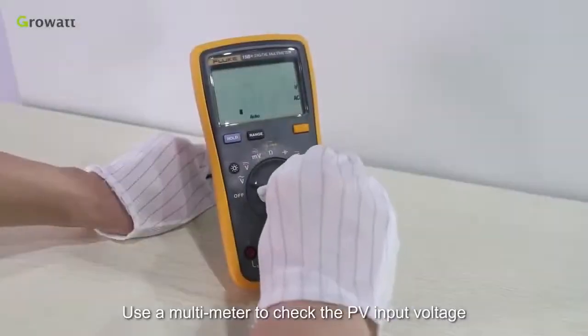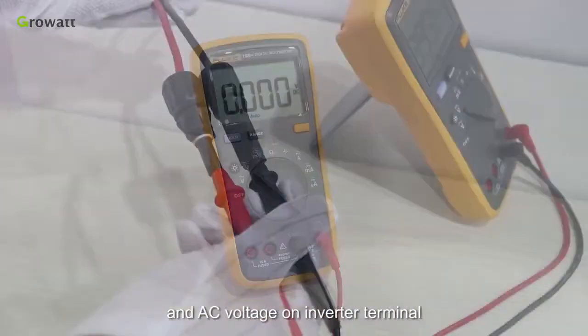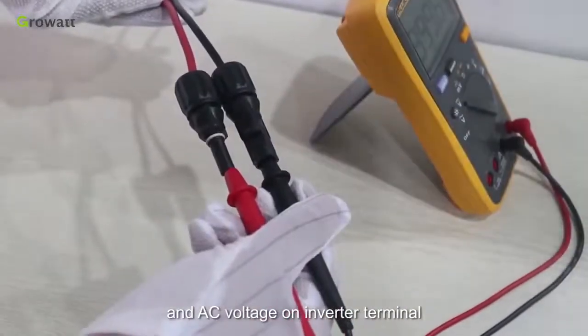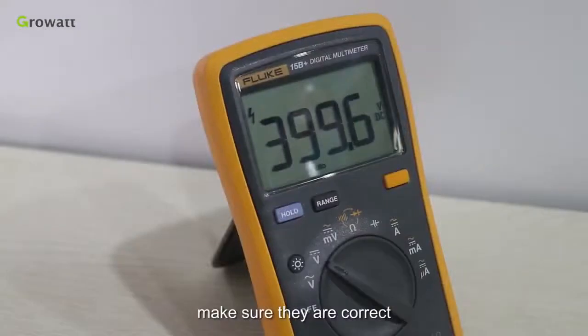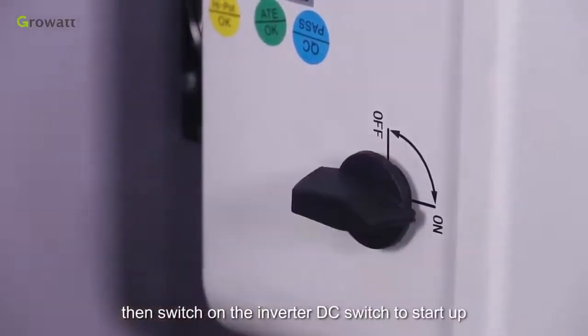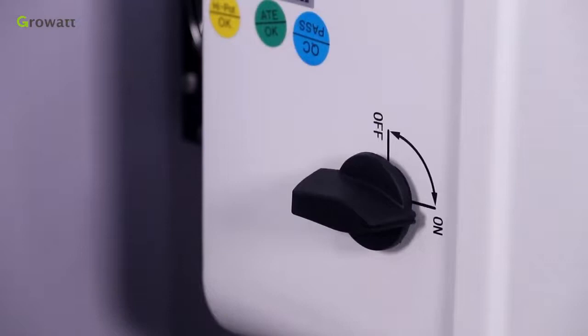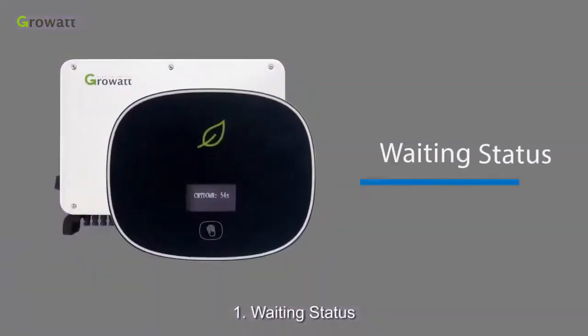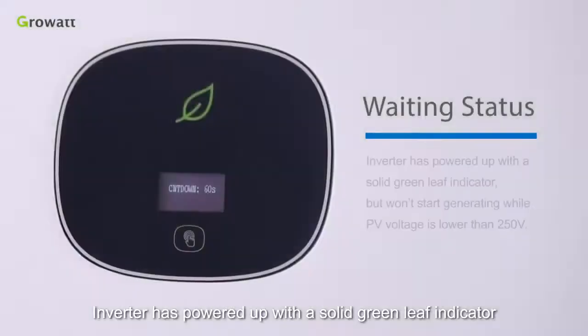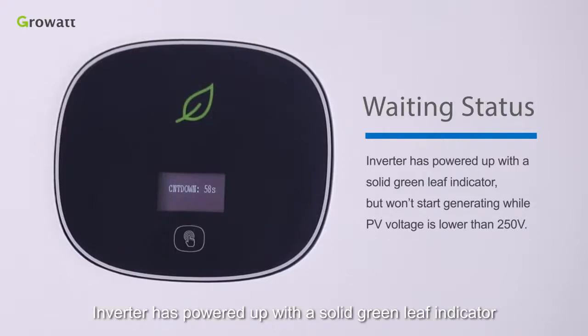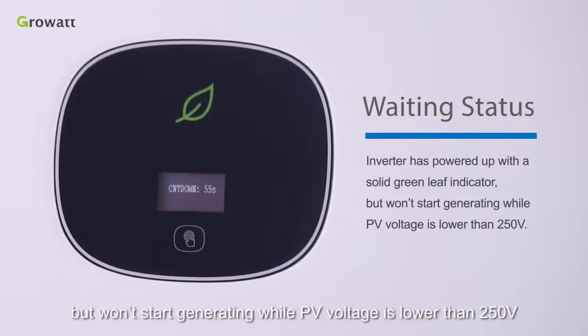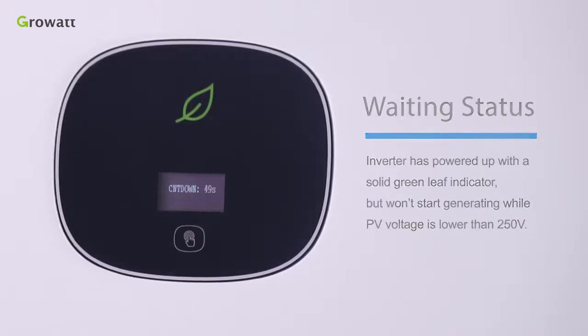Use a multimeter to check the PV input voltage and AC voltage on the inverter terminal. Make sure they are correct, then switch on the inverter DC switch to start up. 1. Waiting status. The inverter has powered up with a solid green leaf indicator, but won't start generating while PV voltage is lower than 250 volts.